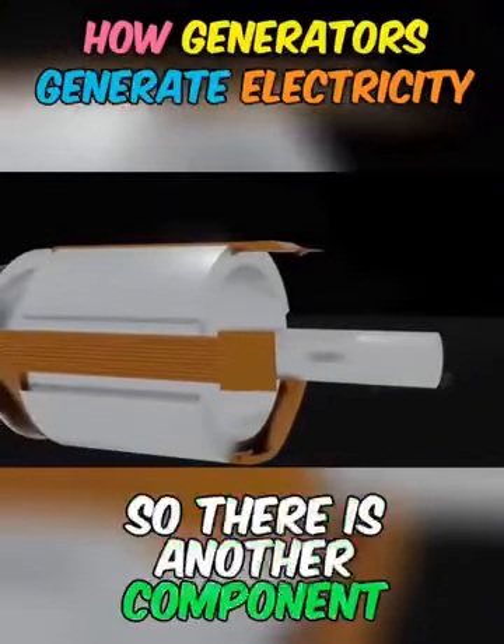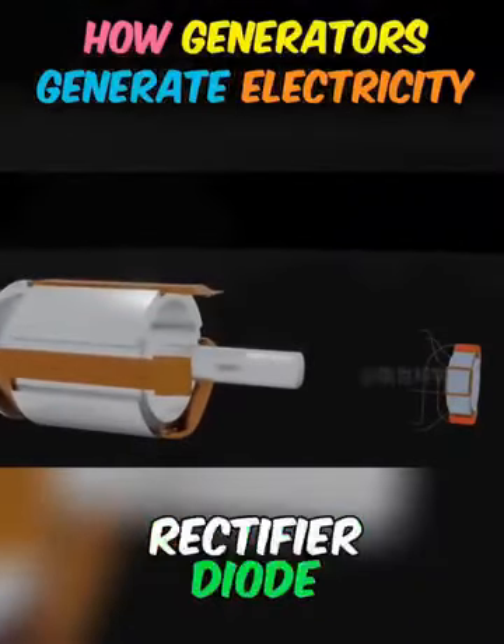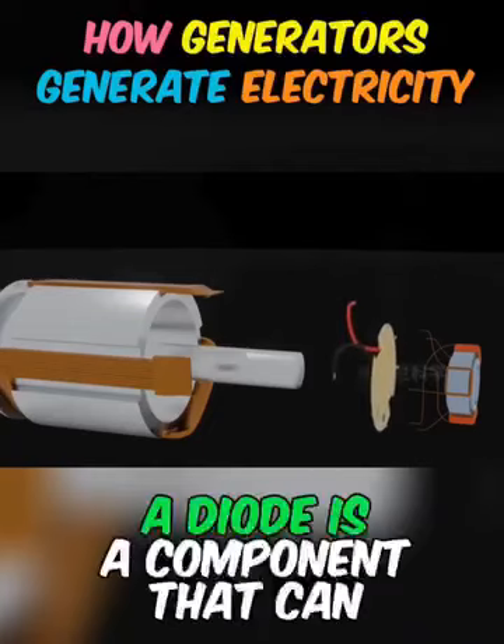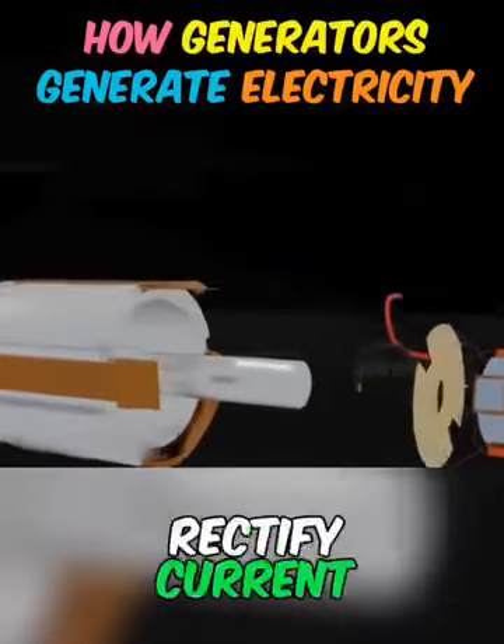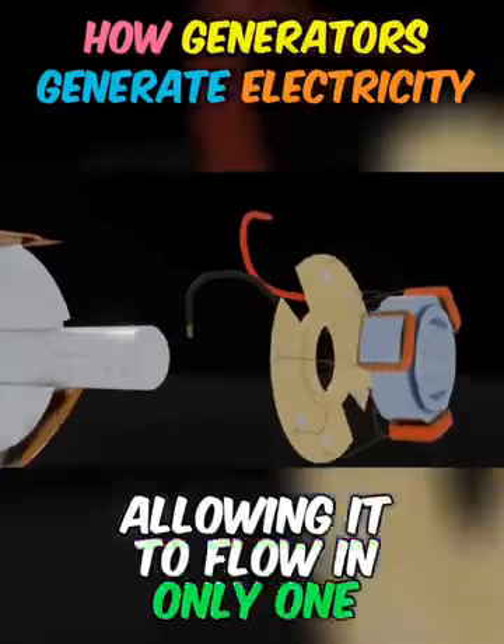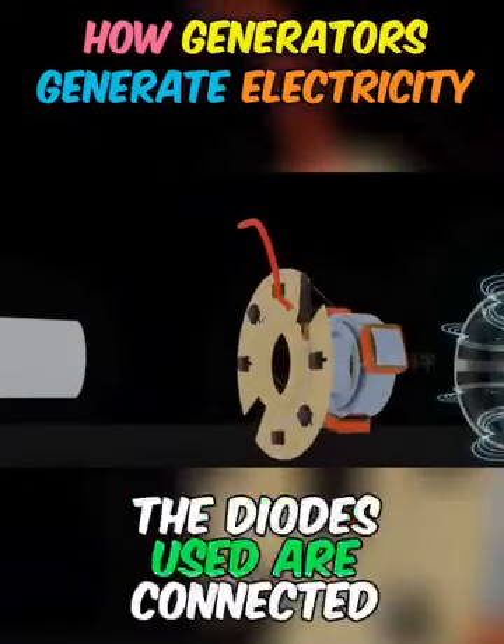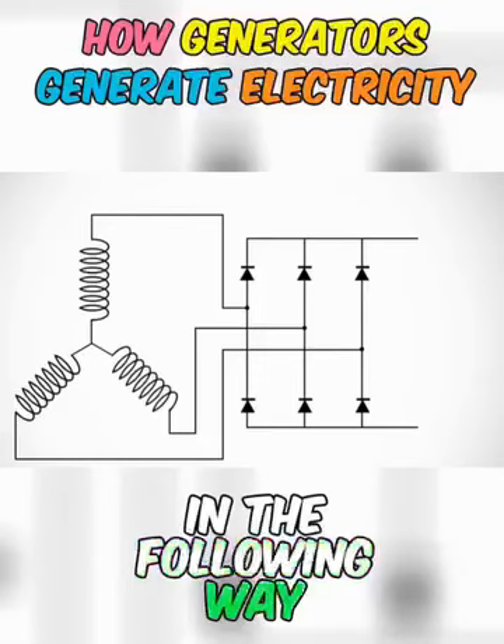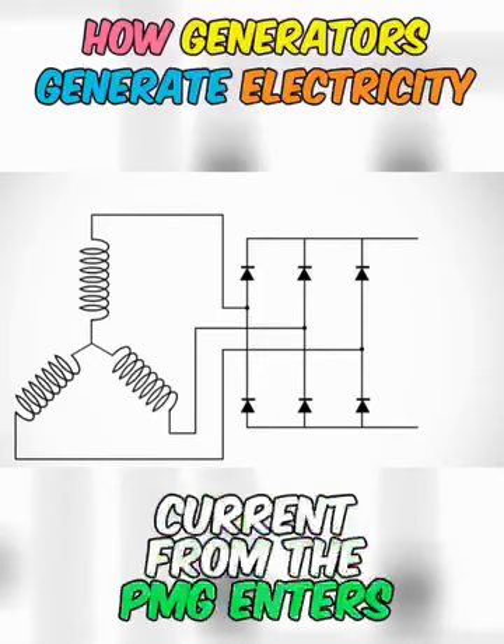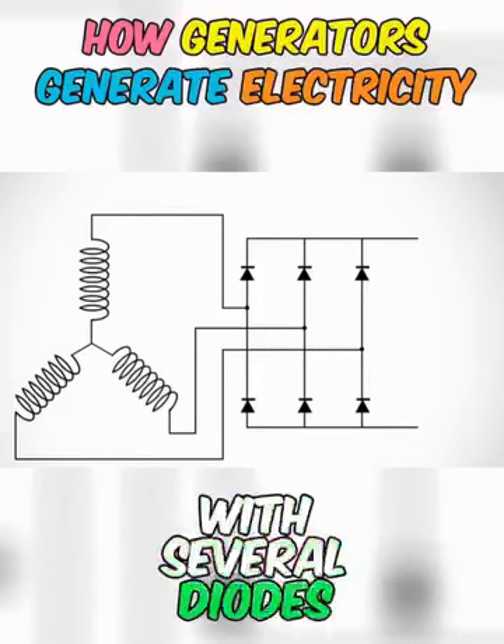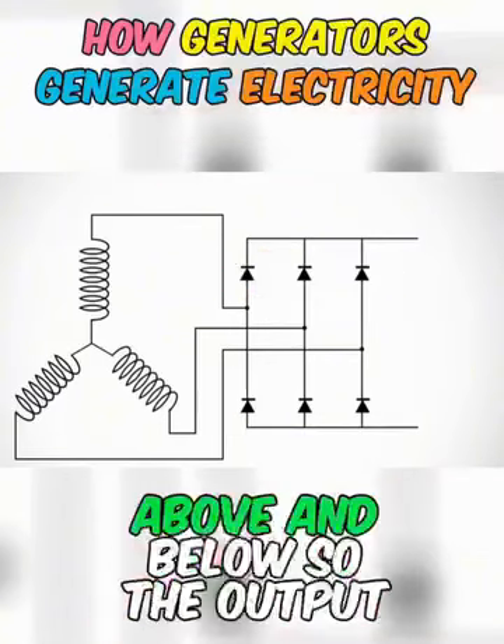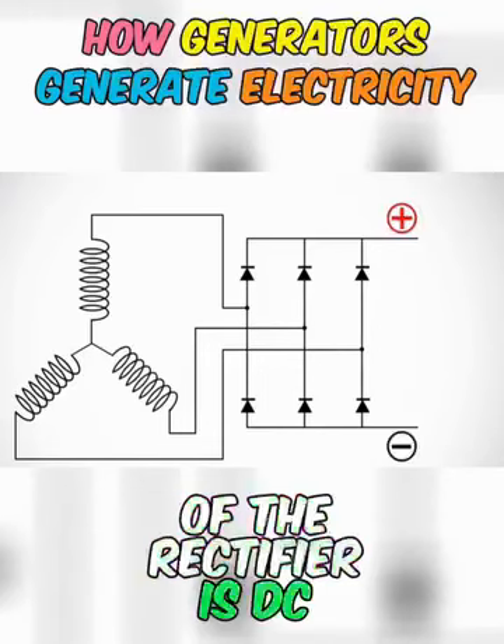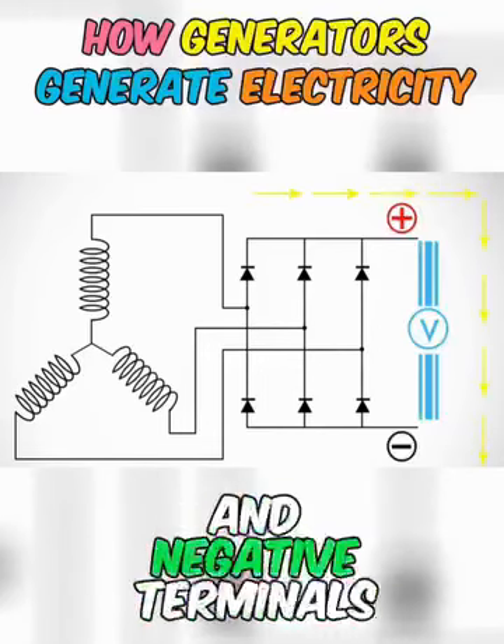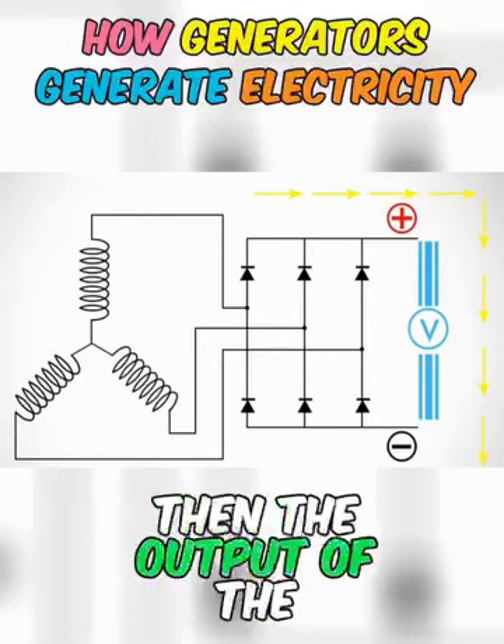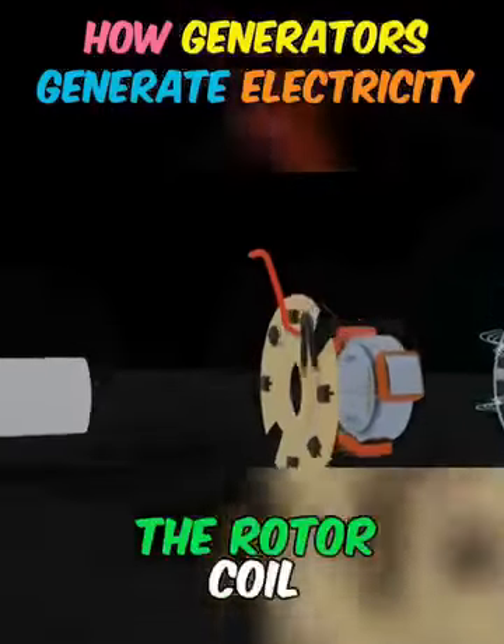So there is another component: rectifier diode. A diode is a component that can rectify current, allowing it to flow in only one direction. The diodes used are connected in the following way. Current from the PMG enters from the middle, with several diodes installed in the same direction above and below. So the output of the rectifier is DC transmitted through the positive and negative terminals. Then the output of the rectifier is transmitted to the rotor coil.